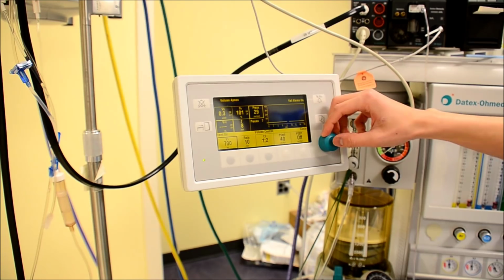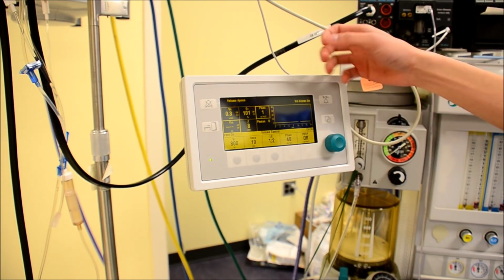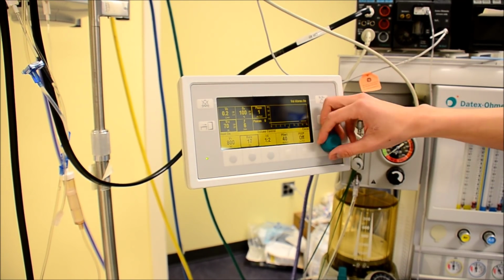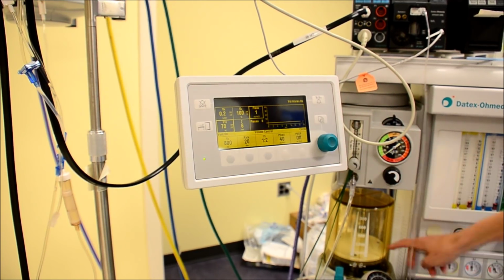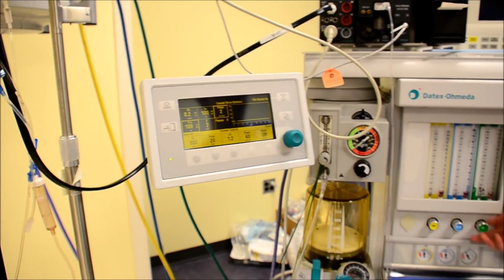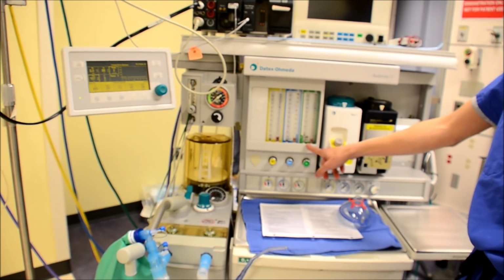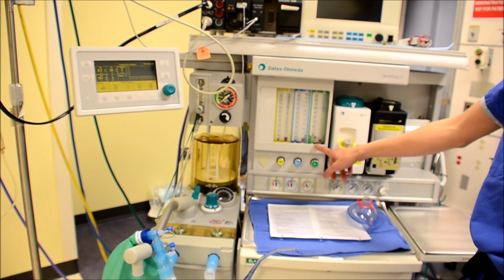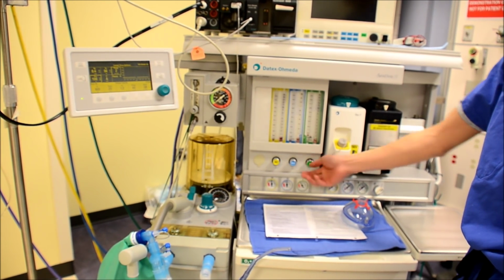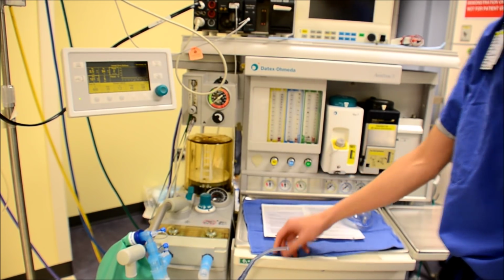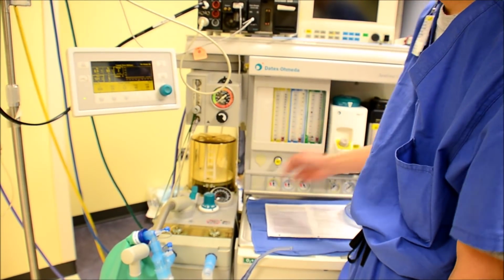What you can do is you can increase it up to however much you want. So we'll say 800, and it'll make it increase your rate to 20, so it gets these bellows to fill a little bit quicker. Go ahead, and we're going to test the ventilator at two different types of flows. We'll do low flow at ½ a liter. And as you can tell, there's not enough flow to get the bellows to rise.